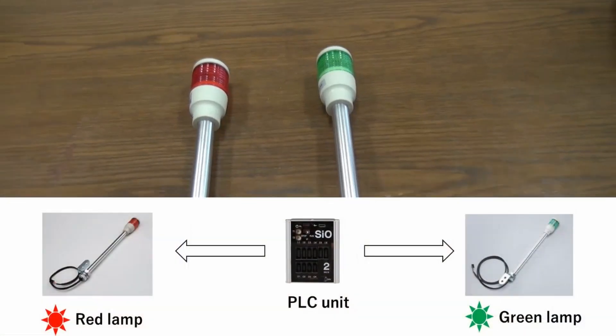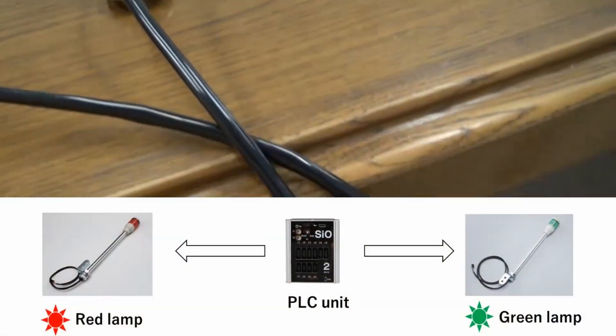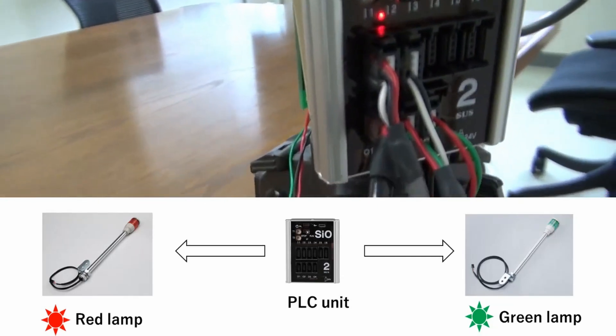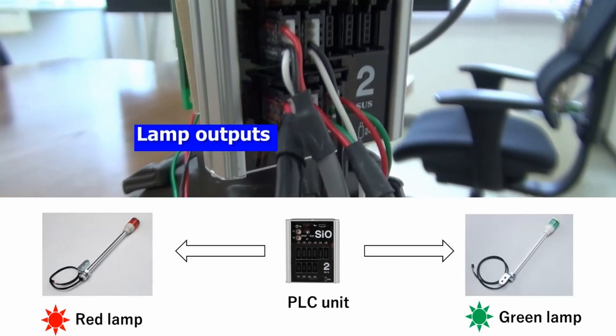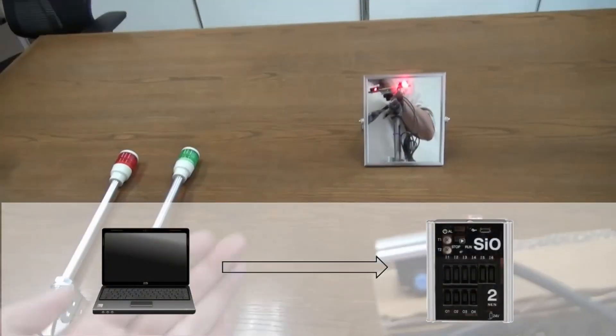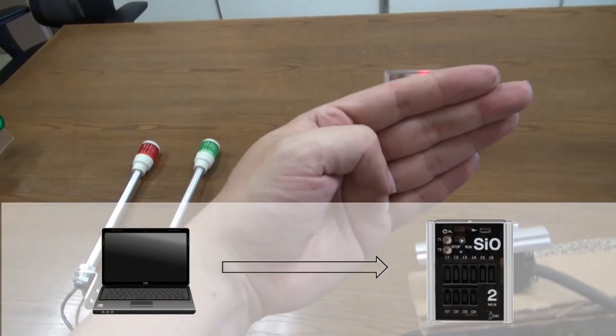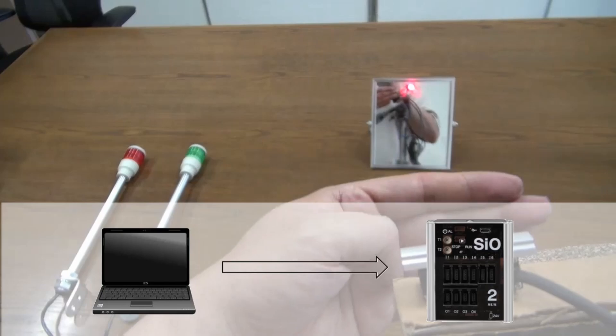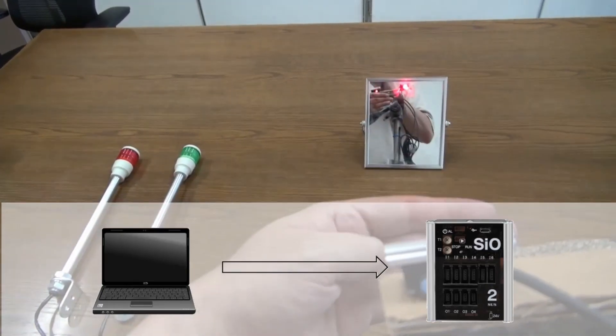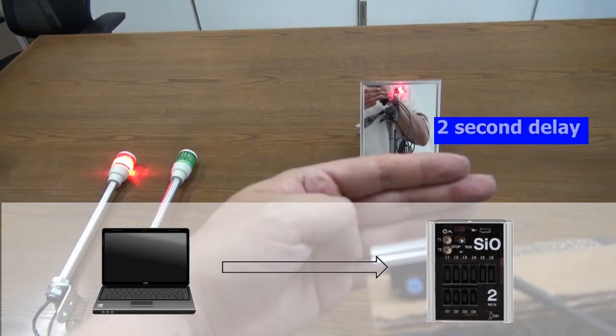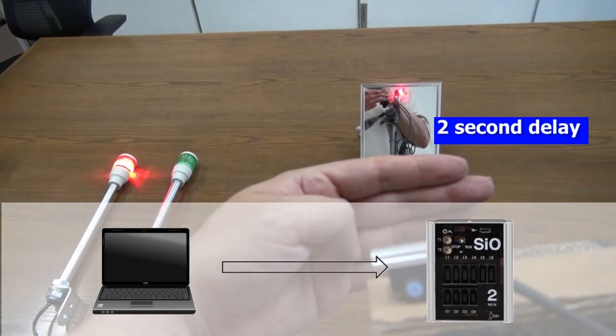Both the beam sensor and the button can be plugged into a PLC unit using the appropriate connectors. We can install two lamps corresponding to the sensor and the button, connected to the PLC output with appropriate connectors. The PLC can be programmed depending on how we want it to treat the output when it receives an input. In this example, we program a two-second delay when the beam is broken so that we can ignore momentary triggers.